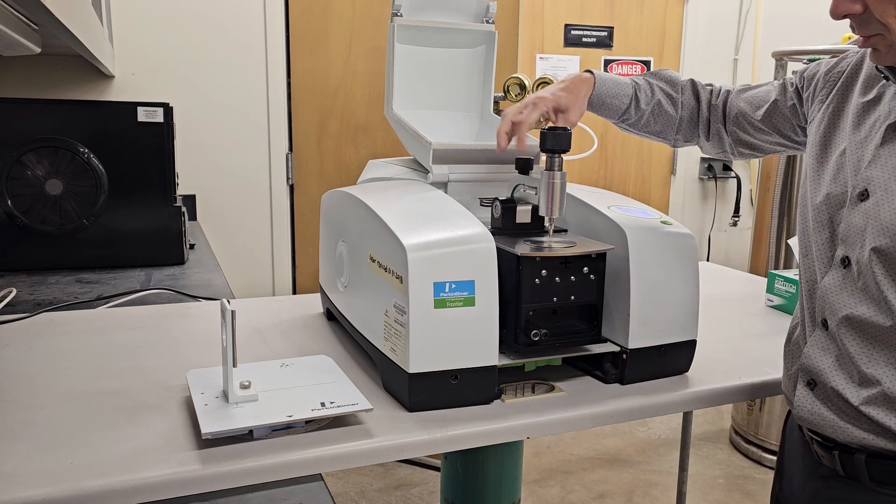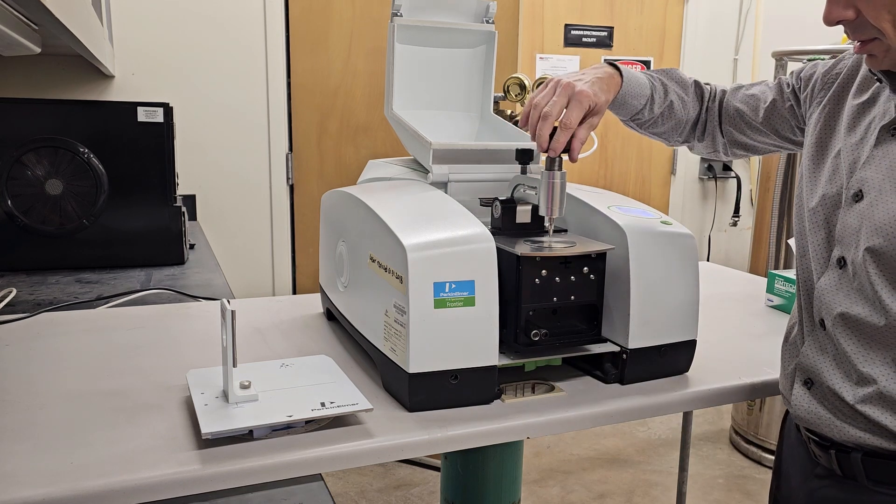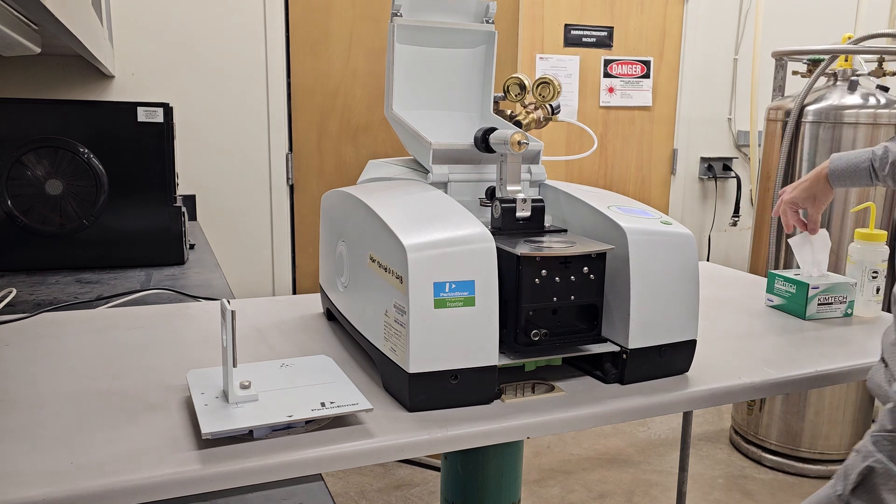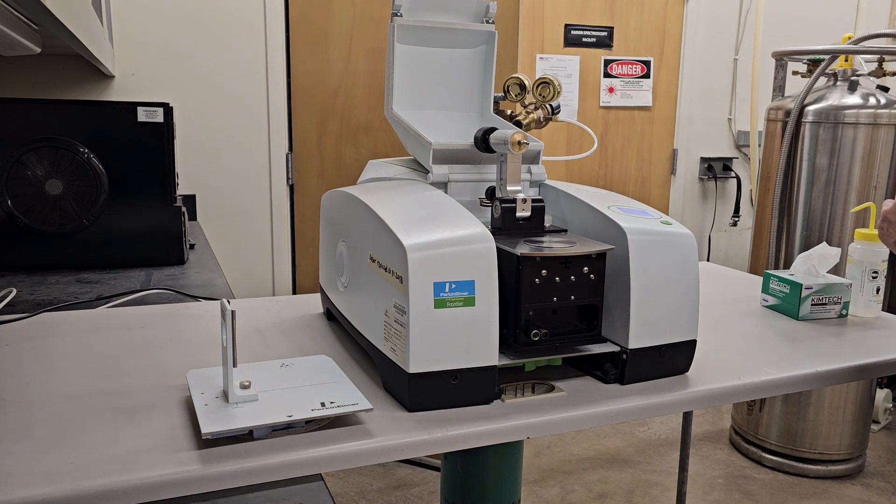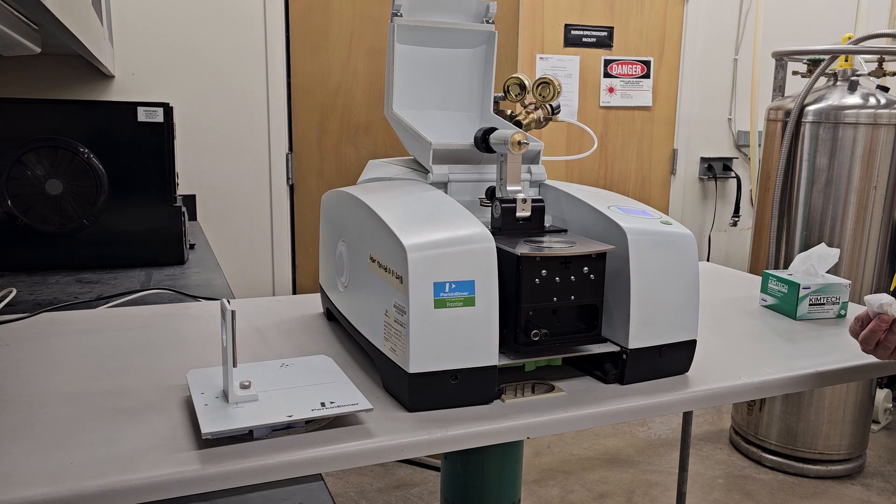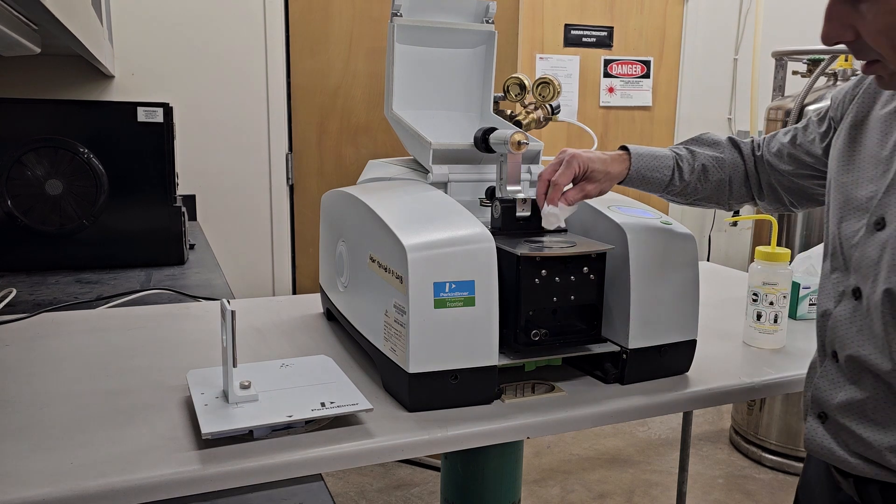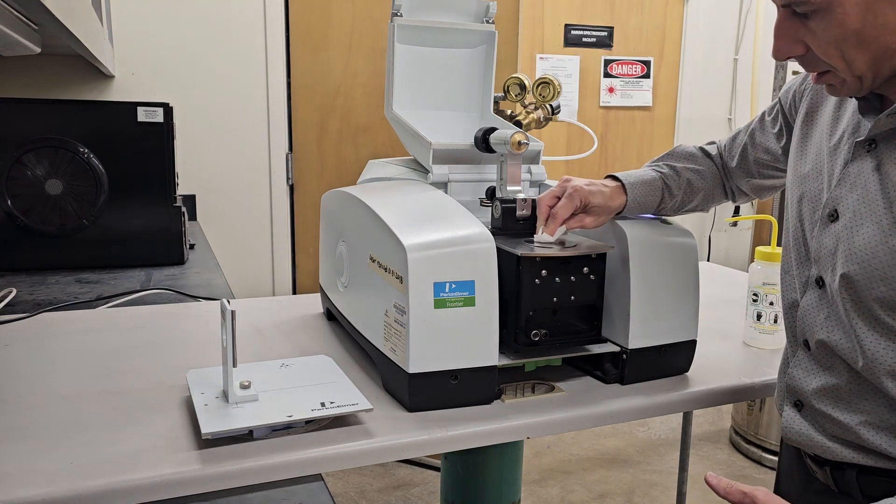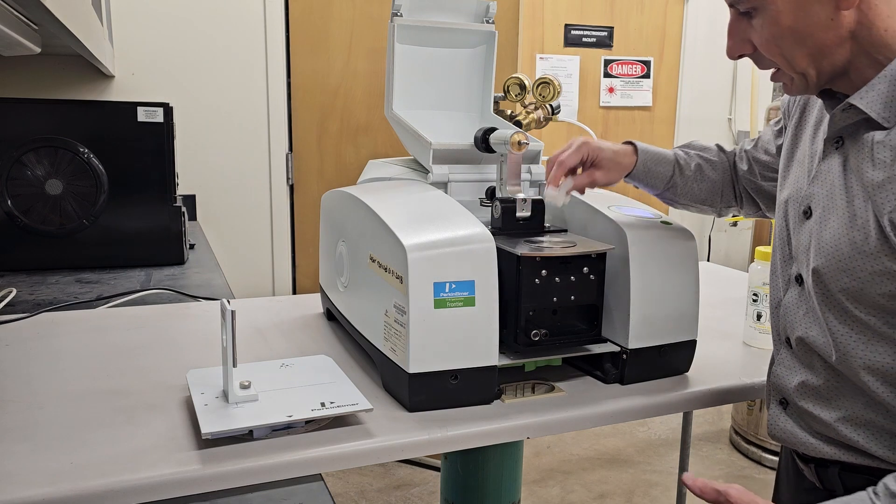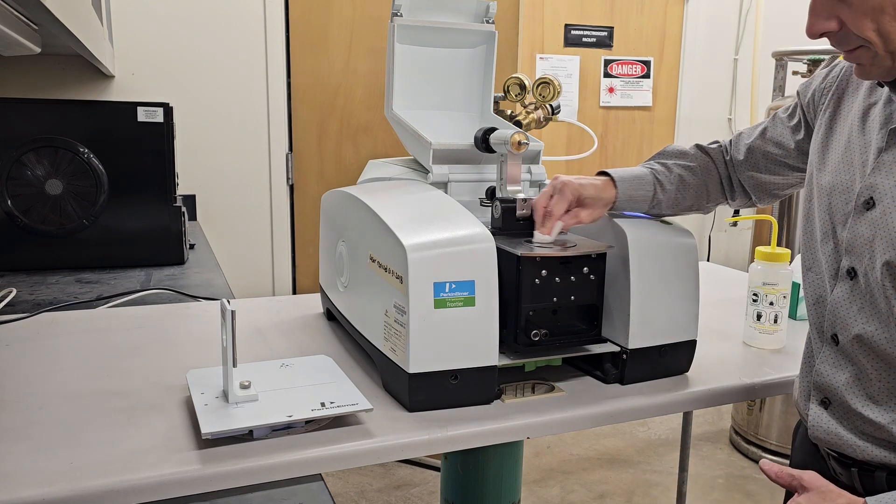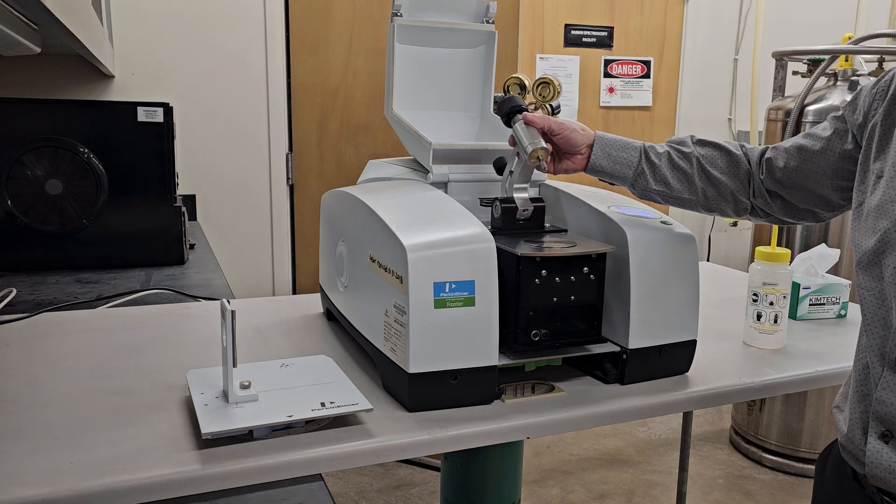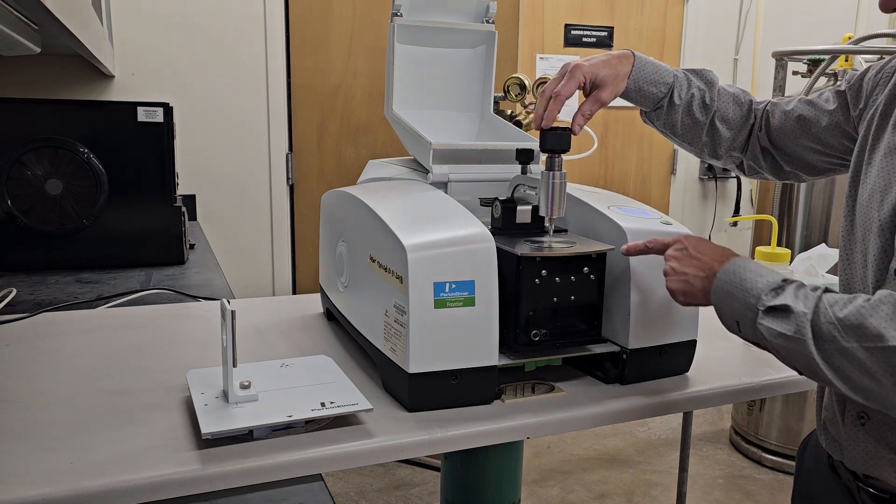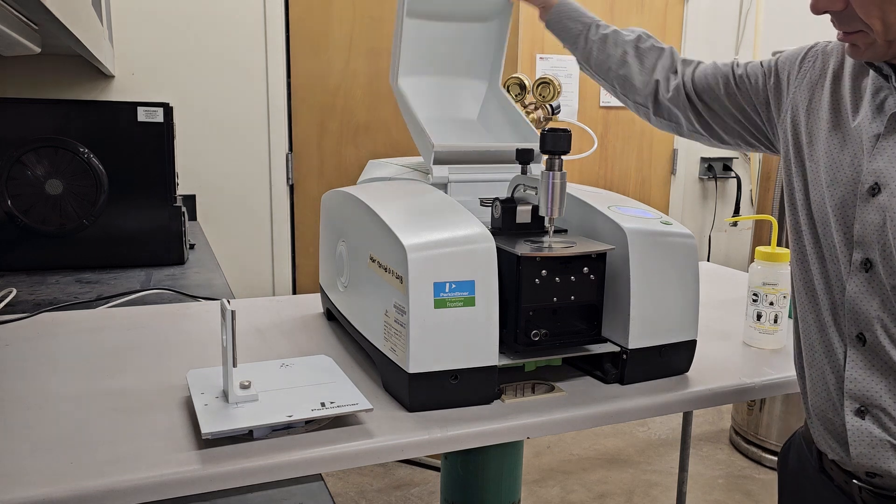Release the small knob, move the arm back and clean the Diamond with a chem wipe and some alcohol. Bring the arm back down, being sure that the tip does not touch the ATR.